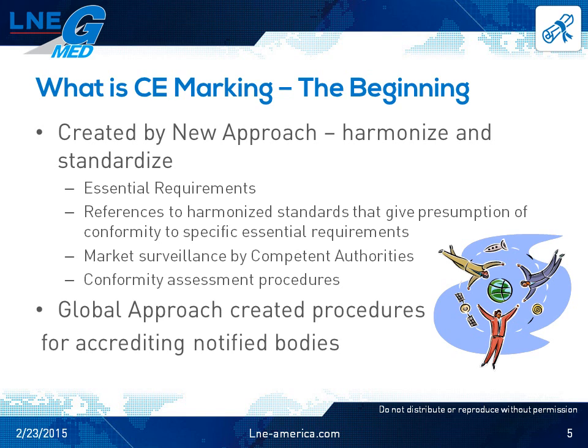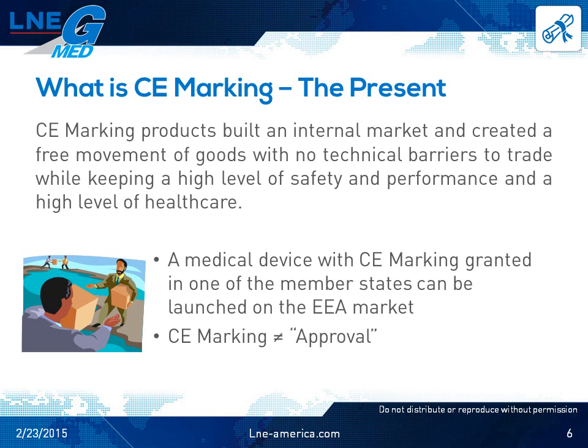After the New Approach came the Global Approach, which helped to create the procedures for accrediting or notifying the various notified bodies. As a result of the New Approach and CE marking, the EEA has an internal market with free movement of goods and no technical barriers to trade. This means that a medical device with a CE marking that was granted in one of the member states can be launched on the EEA market as a whole generally.